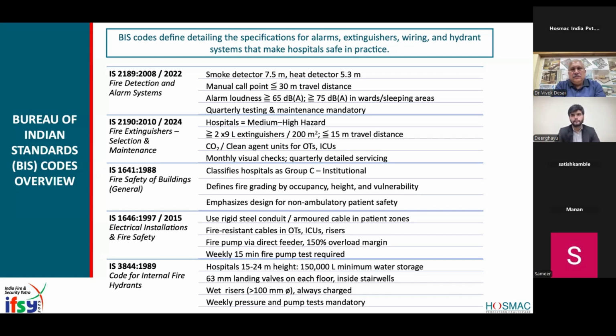the hospitals. And the fire pump, when we design it, the criteria is that it should take 150% of the water load. So when the pump is operated, it should not fail when multiple outlets are being used by the fire officer. Because of overload, the fire pump will trip or burn. So that's the criteria, that it should consider a 150% overload margin.